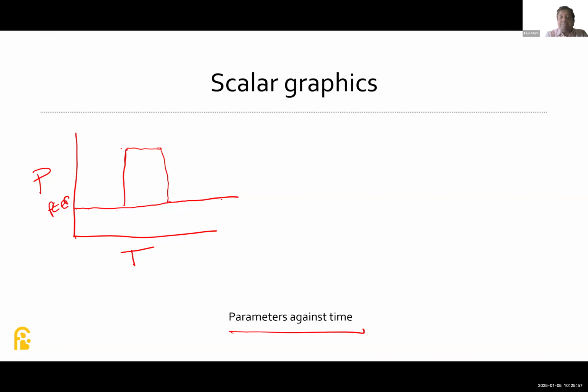And then PEEP will be there throughout the expiratory cycle, because this will try to prevent the baby from having any collapse. Then again one more breath will get generated, and it will again stay till the end of inspiration, and then you will have an expiratory breath, the expiration which will get started in that respiratory cycle, and the child will be on the PEEP. This is how typically your pressure versus time curve will be.